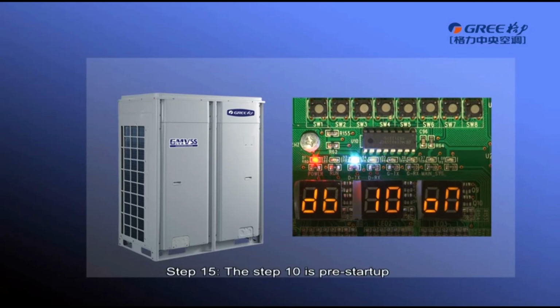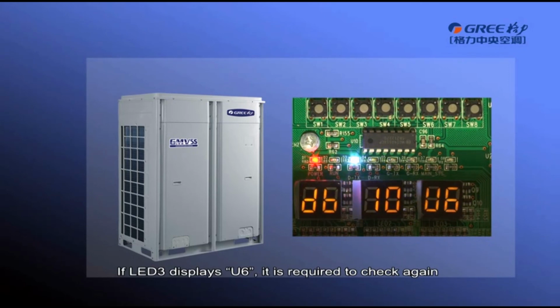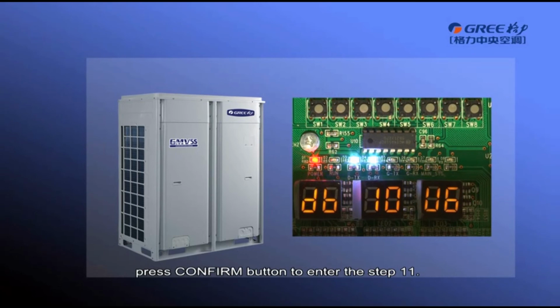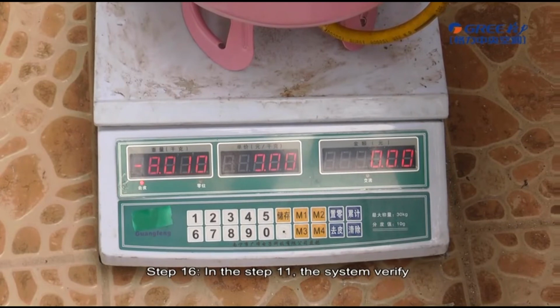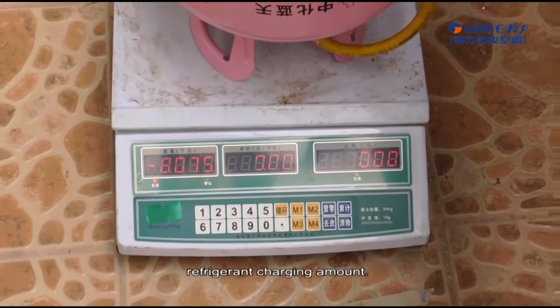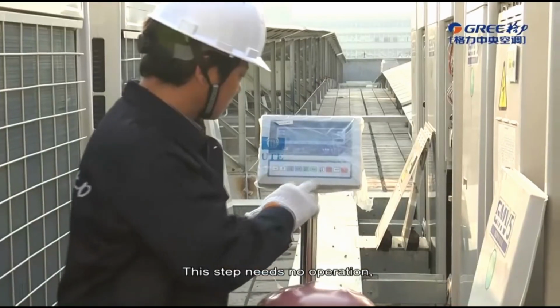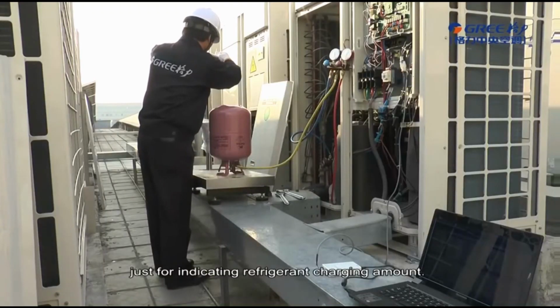Step 10 is pre-startup outdoor unit valve status detection. If LED 3 of master module displays on, it indicates that the unit is being enabled. If LED displays U6, it is required to check again whether the outdoor unit valves are opened completely. After confirming that all valves are opened completely, press confirm button to enter step 11. In step 11, the system verifies refrigerant charging amount. This step needs no operation, just for indicating refrigerant charging amount.